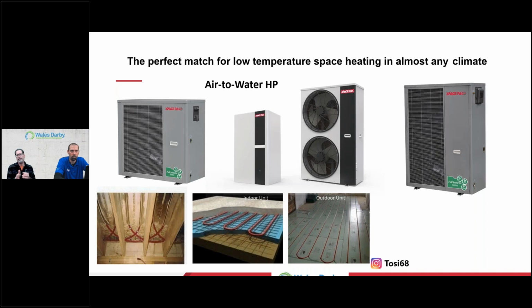That was some of the beauty about stepping into high efficiency, maybe with an existing clientele who's already hydronically based. They're coming to you and they want to get rid of this old dinosaur, but I'm like, hold on a second, don't just dismiss it. You might want to leave it. How about if we add something that's going to carry the load at lower water temperature for a good chunk of your heating season, and only then do we turn on the boiler as backup? This is what I said earlier about having redundancy. Unless space is at a premium and they need to get rid of it, be very cautious about immediately saying it's got to go.